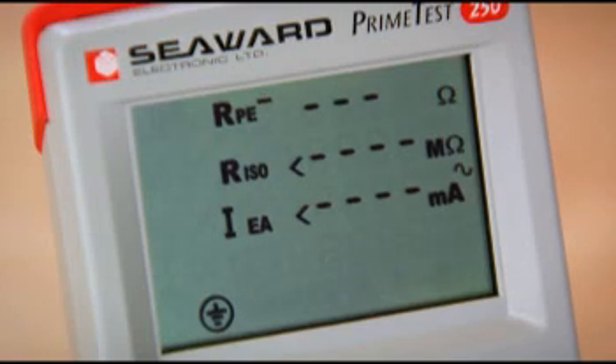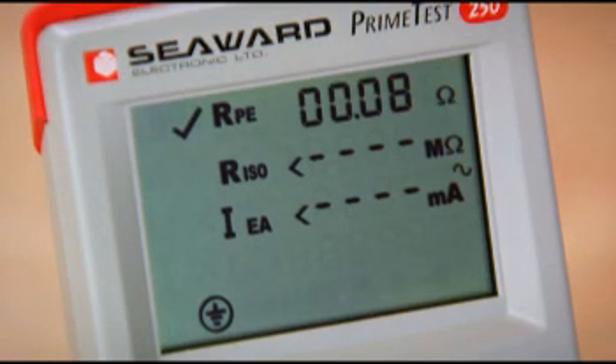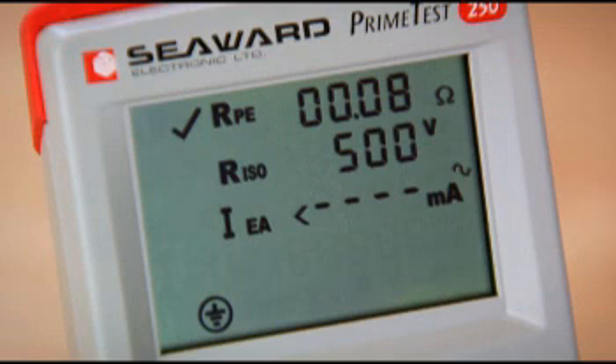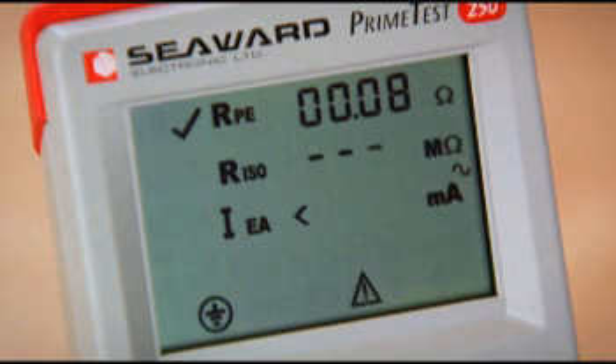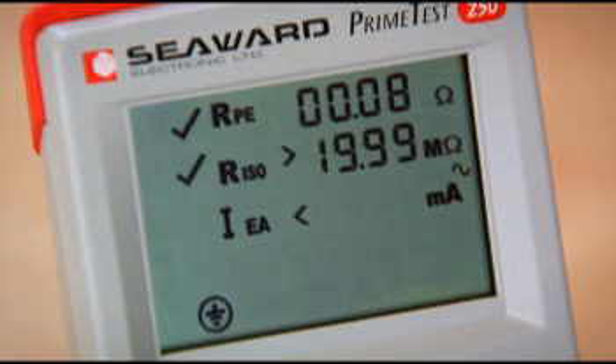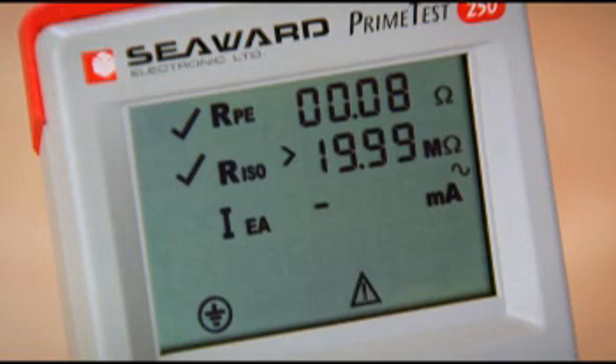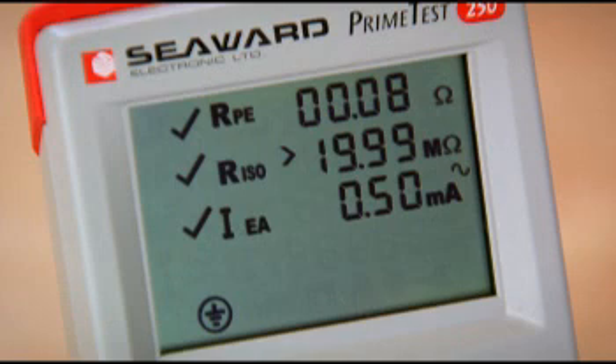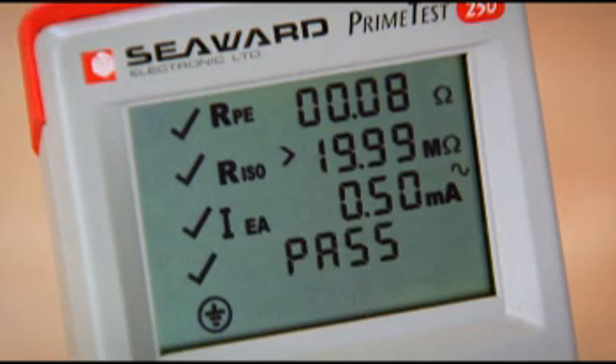First of all, the tester is performing the earth continuity test. Now the insulation test at 500 volts. And now it's going to measure leakage current using the internal voltage supply because we have no incoming mains. The sequence is now finished and it's showing the overall result as a pass.